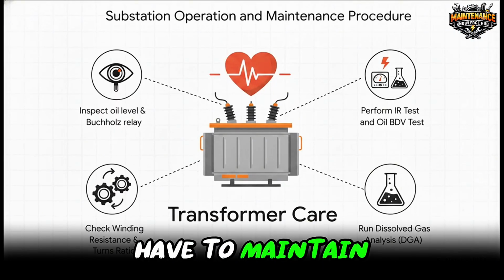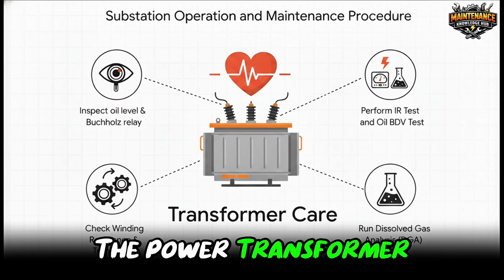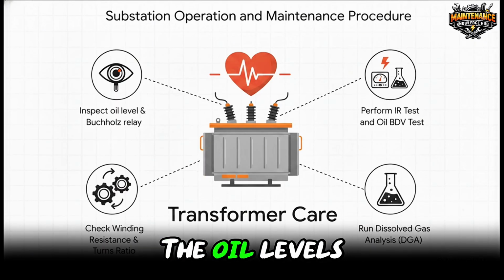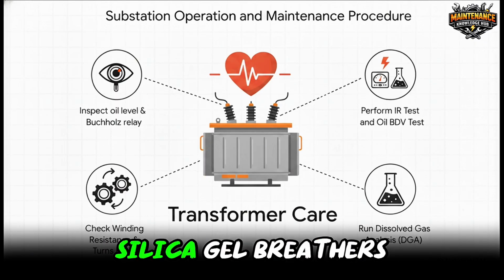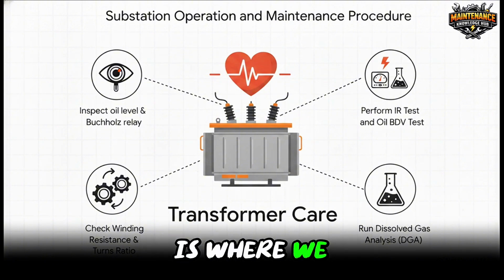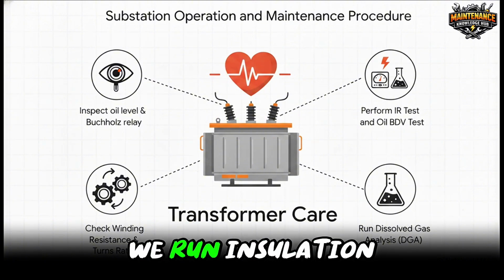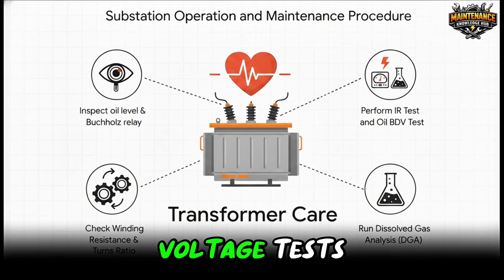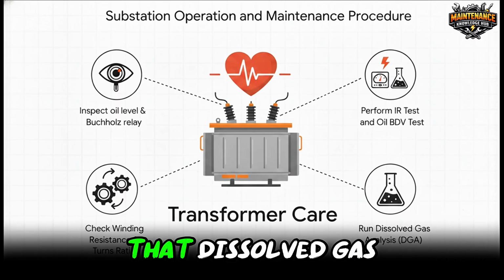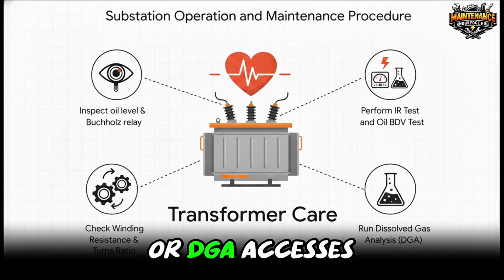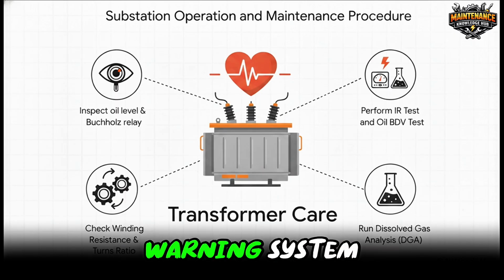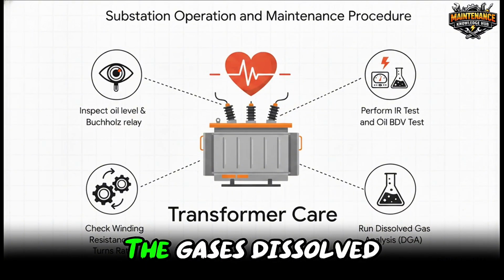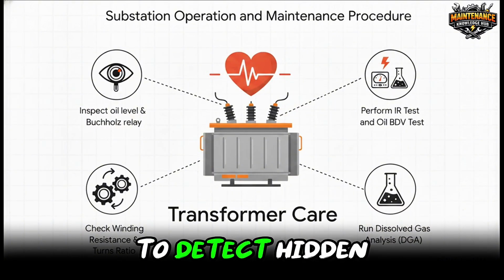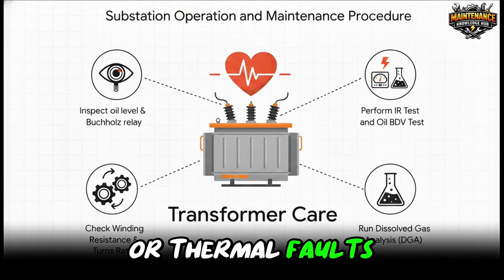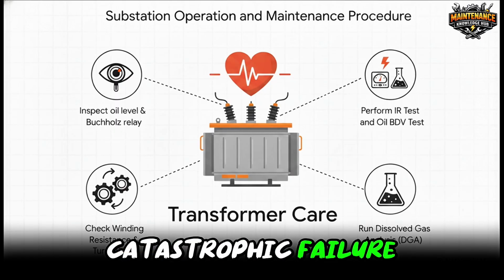First up, we have to maintain the heart, the power transformer. Visual inspections handle the oil levels, the Buchholz relay, and the silica gel breathers. But the testing is where we really catch those early failures. We run insulation resistance and breakdown voltage tests, but most critically, that dissolved gas analysis, or DGA, acts as our ultimate early warning system. It literally analyzes the gases dissolved in the oil to detect hidden internal arcing or thermal faults long before they can cause a catastrophic failure.